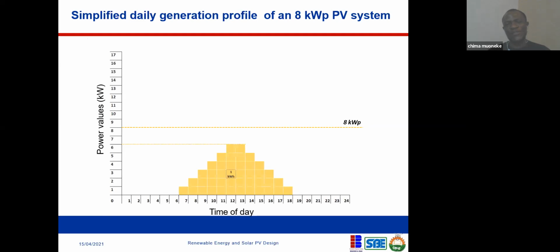On a good sunny day, this is how your solar PV will perform: the sun comes out around 7 and dies down around 6, reaching peak around 12:01. Assuming this is an 8 kilowatt peak solar system, it doesn't actually hit 8 kilowatts because of losses and the performance ratio—that's the gap you see here. So this is the highest it's able to do on a typical sunny day, the solar generation profile.